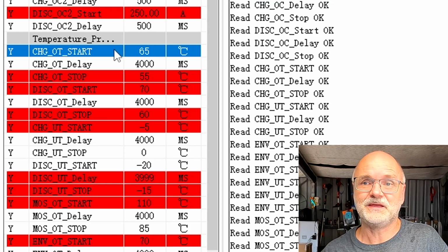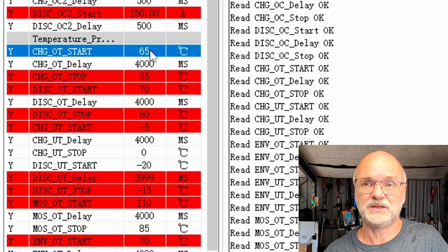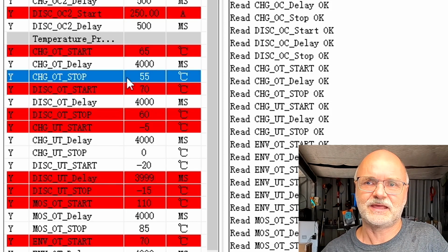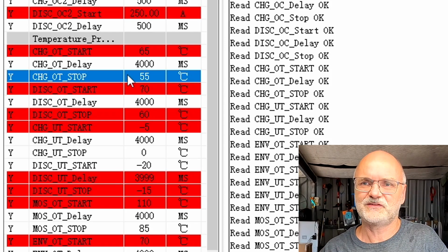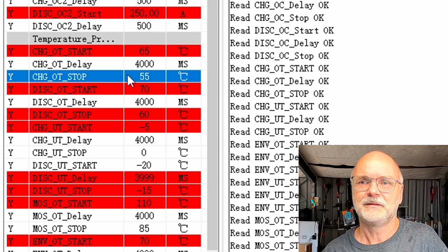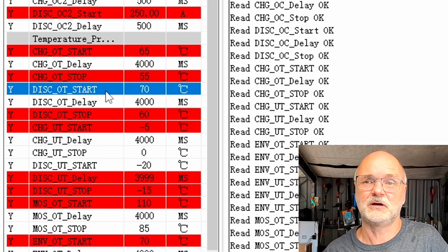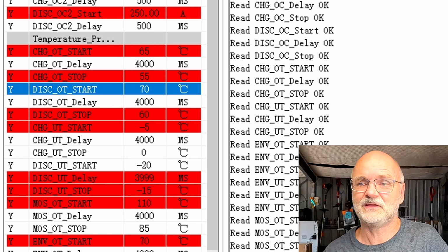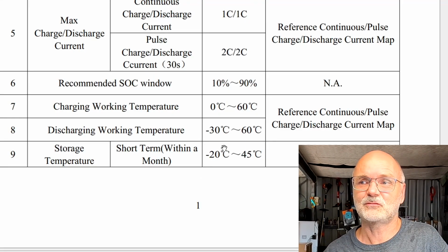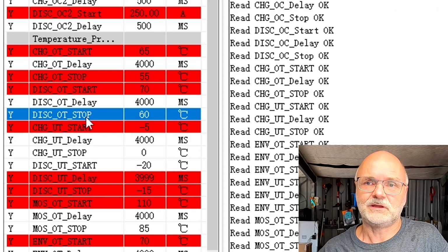So here we've got a parameter which is completely wrong. This should be at 60 degrees, or I would even set this one to 50 degrees maximum. I mean, this is already so hot, and it would allow charging again at 55 degrees. So these 2 parameters I would really like to change at least 10 degrees down. And the discharge over temperature is at 70 degrees, which is again 10 degrees higher than the specification of this battery. And then at 60 degrees, it allows discharging again, far too hot.